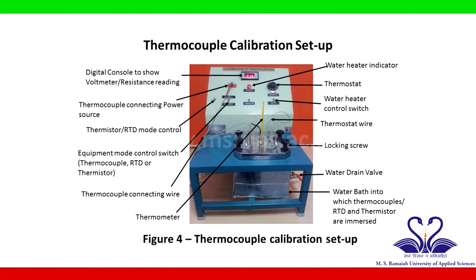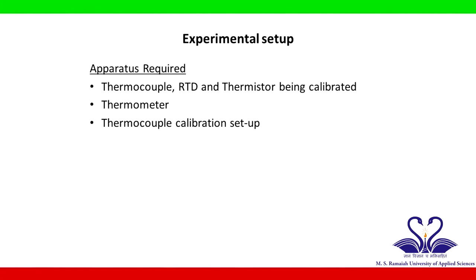The setup consists of a water heater indicator, a thermostat, a water heater control switch, a thermostat wire, a water bath, 4 locking screws to close the water bath, water drain out valve, K-type and J-type thermocouple, an RTD element, a thermistor, a thermometer, an equipment mode control switch, a thermistor RTD mode control switch, a power source and a digital console to show the voltage or resistance reading. The apparatus required for carrying out this experiment are the thermocouple, RTD and thermistor which are being calibrated, a standard thermometer, and a thermocouple calibration setup.